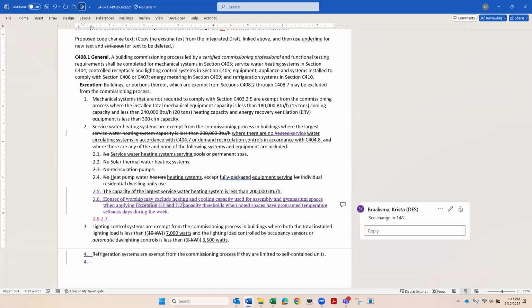And I really don't like this 2.5 down at the bottom there. This says that you get out of this if the largest water heating system is less than 200,000 BTUH. But what it is now is that it's the sum total of them is 200,000 BTUH, and it would be very easy to say, well, we got this one for the West Wing and this one for the East Wing, and therefore we're below 200,000. So it should say the capacity of the combined service water heating systems is less than 200,000.